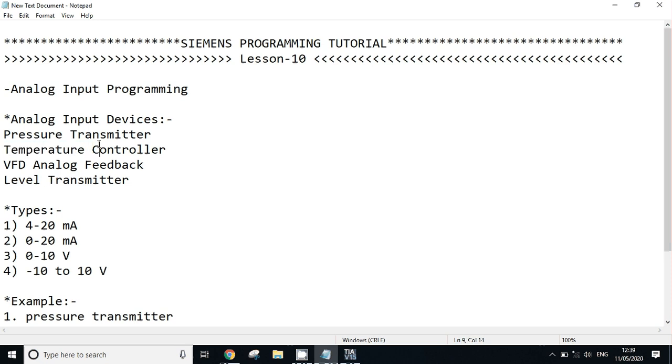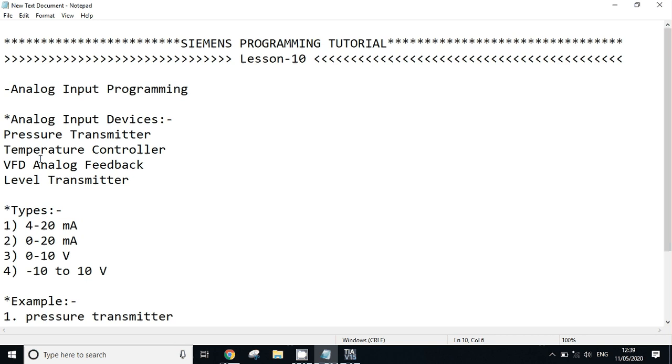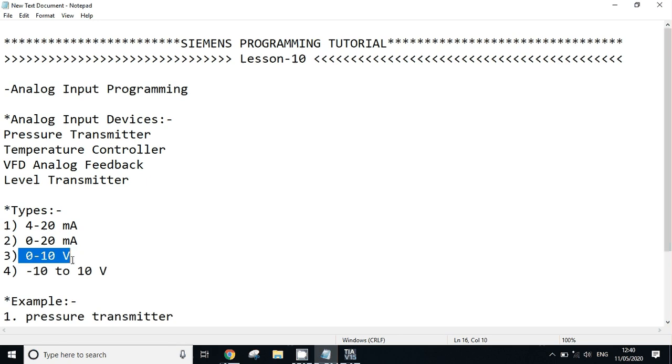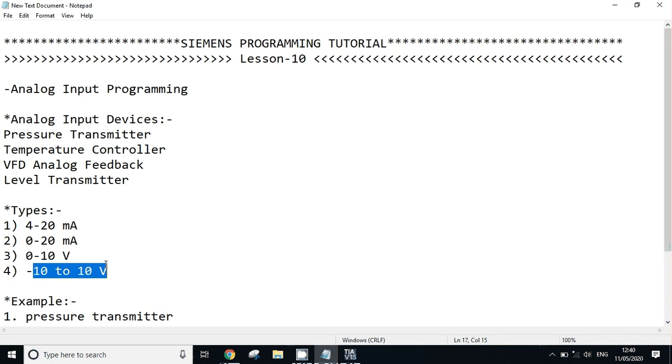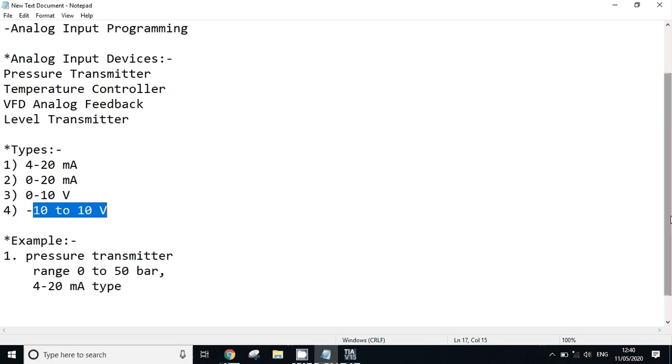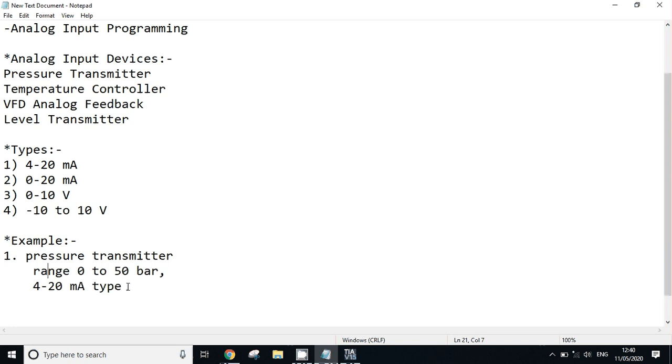What could be the types of these input devices? It could be 4 to 20 milliampere, 0 to 20 milliampere, 0 to 10 volt, or minus 10 to plus 10 volt. In today's video we will take one example - we will consider one pressure transmitter with a range of 0 to 50 bar. The type of this pressure transmitter is 4 to 20 milliampere type, which means it gives 4 to 20 milliampere feedback to our PLC card.